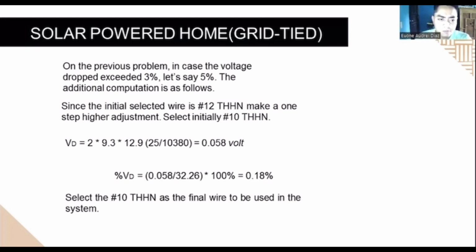On the previous problem, in case the voltage drop exceeded 3%, let's say 5%, the additional computation is as follows. Since the initially selected wire is number 12 THHN, make a one-step higher adjustment. Select number 10 THHN. VD is equal to 2 multiplied by 9.3 multiplied by 12.9 multiplied by 25 over 10,380, which is equal to 0.058 volts. Percent voltage drop is equal to 0.058 over 32.26 multiplied by 100%, which is equal to 0.18%. Select number 10 THHN as the final wire to be used in the system.